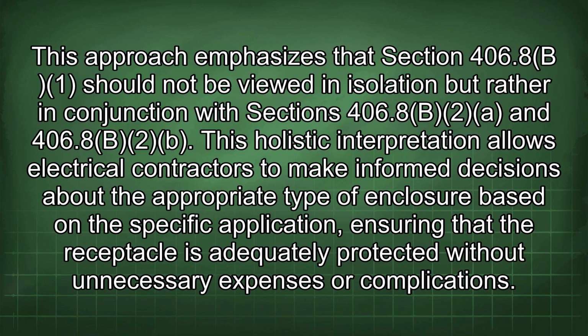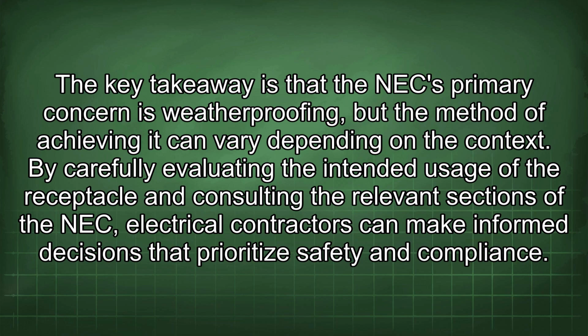This approach emphasizes that Section 406.8(B)(1) should not be viewed in isolation, but rather in conjunction with Sections 406.8(B)(2)(a) and 406.8(B)(2)(b). This holistic interpretation allows electrical contractors to make informed decisions about the appropriate type of enclosure based on the specific application, ensuring that the receptacle is adequately protected without unnecessary expenses or complications. The key takeaway is that the NEC's primary concern is weatherproofing, but the method of achieving it can vary depending on the context. By carefully evaluating the intended usage of the receptacle and consulting the relevant sections of the NEC, electrical contractors can make informed decisions that prioritize safety and compliance.